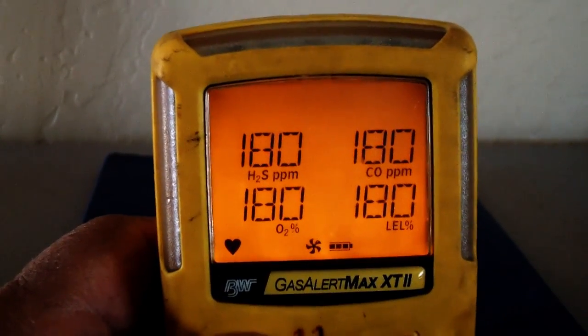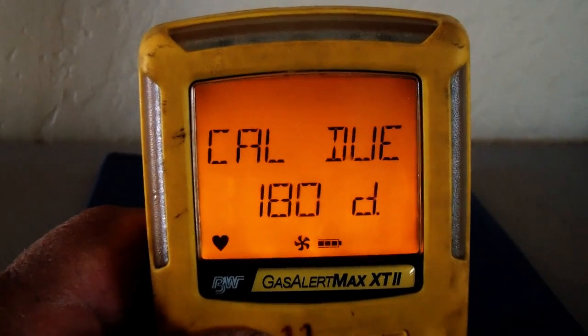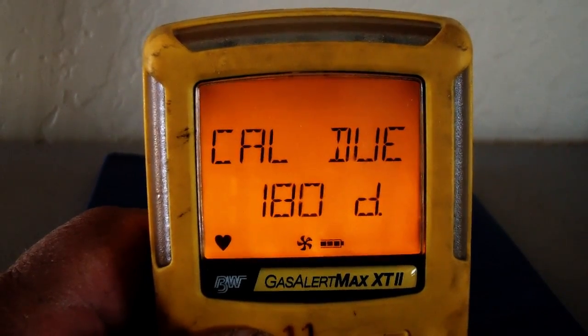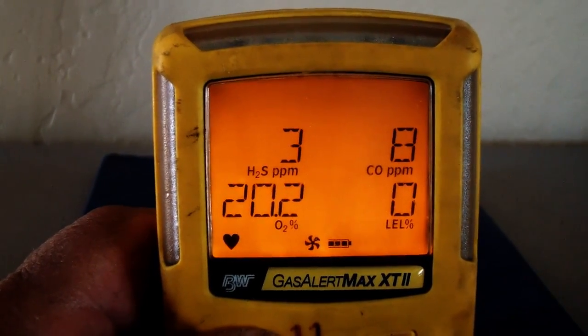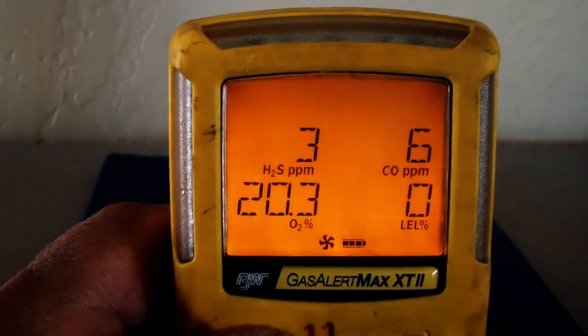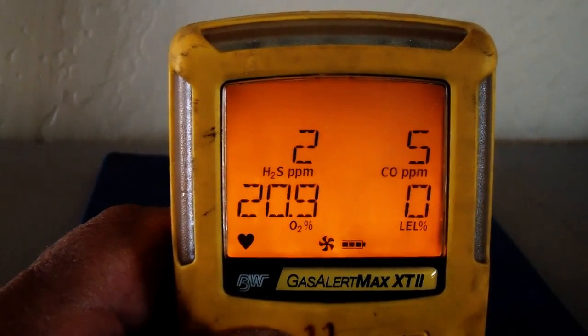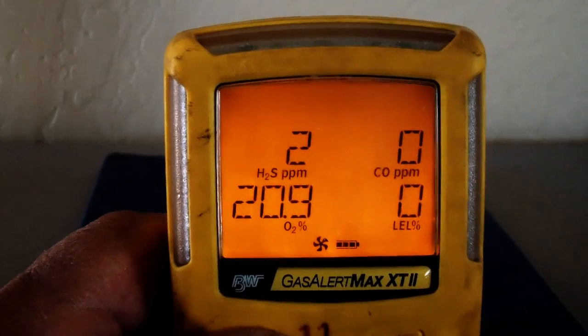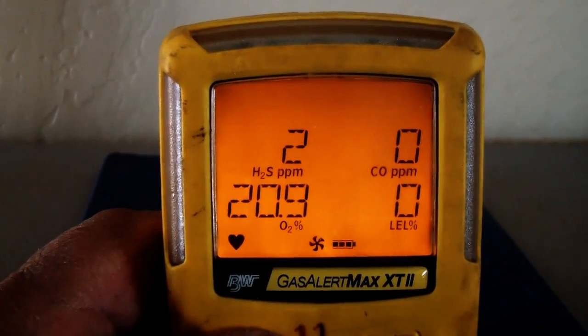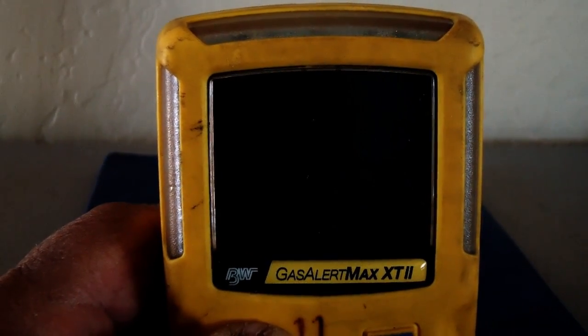So this machine has accepted the calibration. It's telling us that the next time we have to calibrate it is 180 days. We're going to calibrate within 30. And then it's zeroing out on all those sensors and getting back to 20.9 on O2.